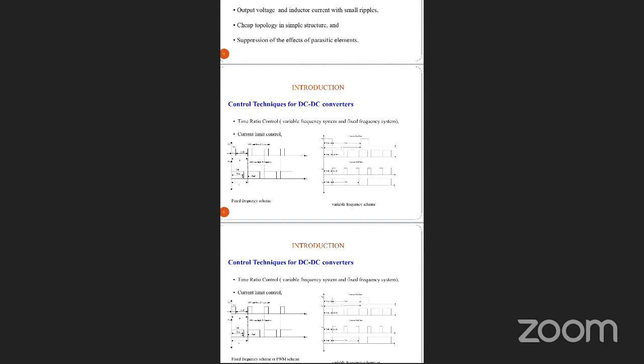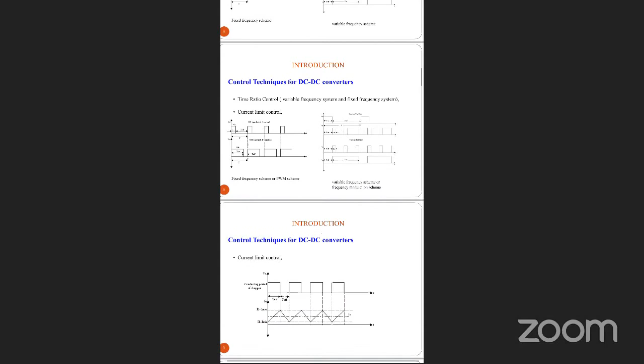Then coming to the next one, the current limit control method. In the current limit control method, the application is very, very important, because we have two control strategies for DC-DC converters. One is the time ratio controller method, TRC. The second one is called the current limit controller, CLC in short form. The current limit control method is only applicable for an inductive load. It is not applicable for a resistive load. That is the first important point.